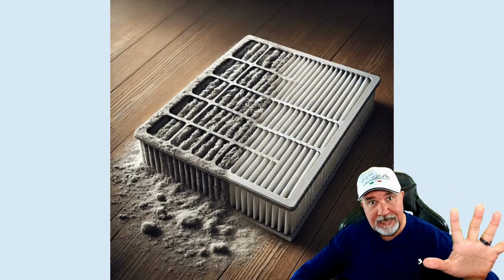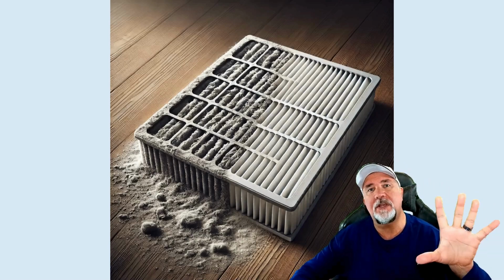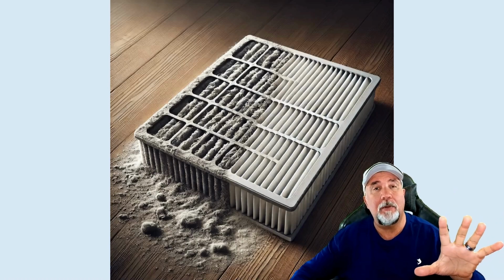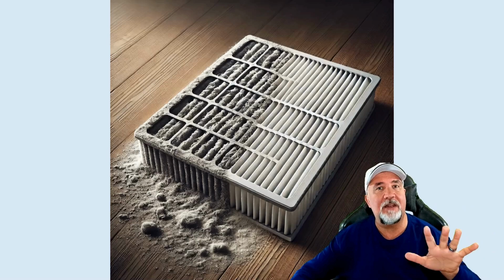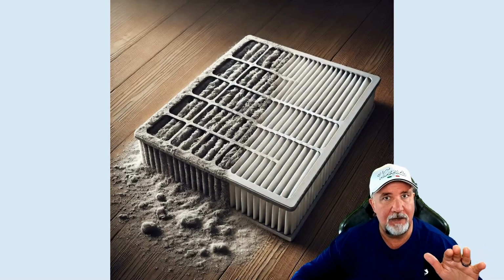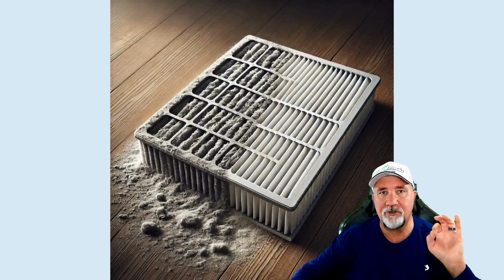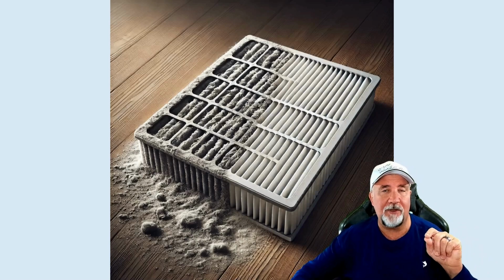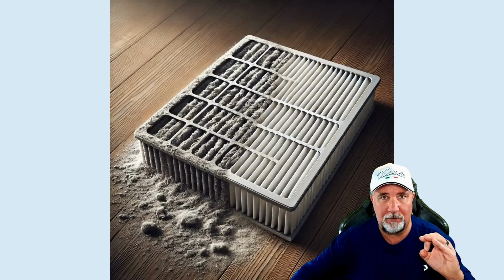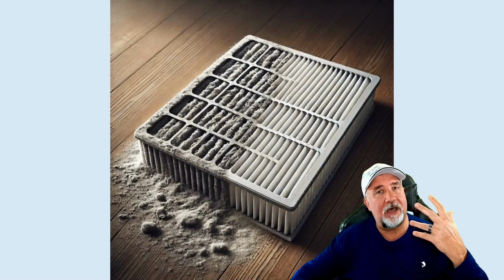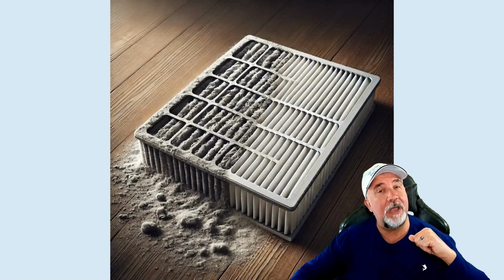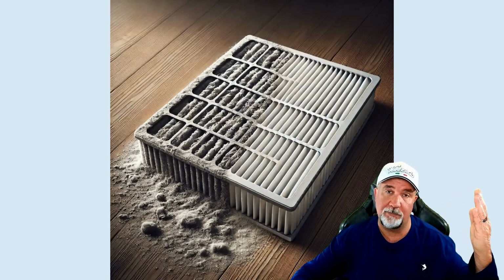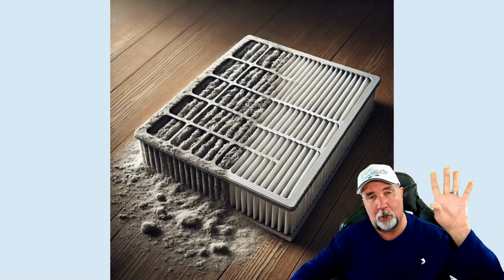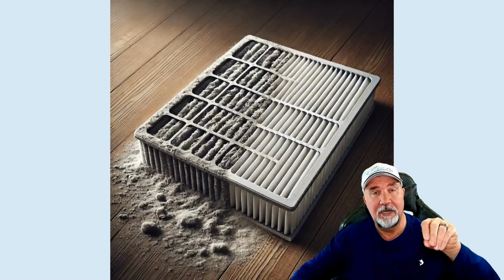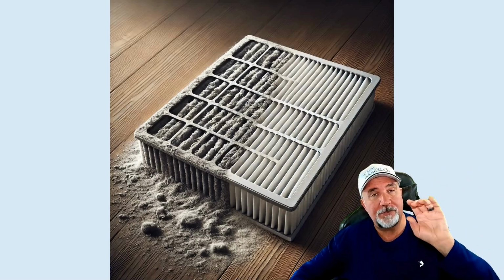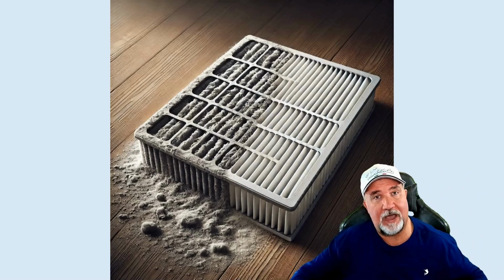Now, once they're cleaned, we need to focus on fixing the problem. The problem is we've got dirt and stuff getting into that ductwork that shouldn't be getting in there. So now we've got to strategize. We've got to play detective and figure out how that is getting in there. That's where the duct testing comes in, to find out how leaky the ductwork is, and also to make sure that we have a good filter, and that the ductwork and the motors are able to handle the restriction of having a much better filter. I don't mean the system isn't large enough tonnage-wise, but the ductwork and whatnot.